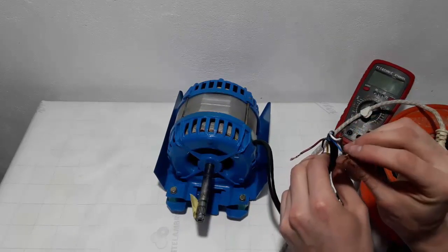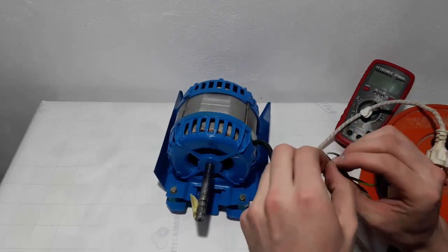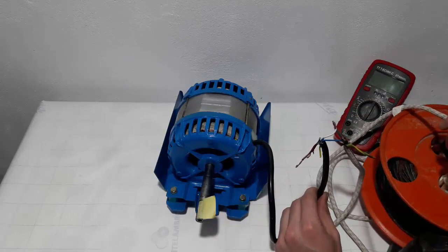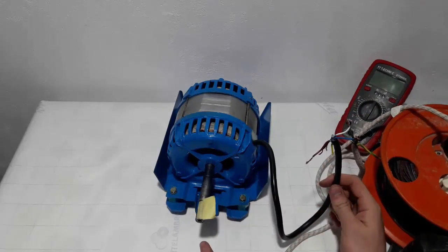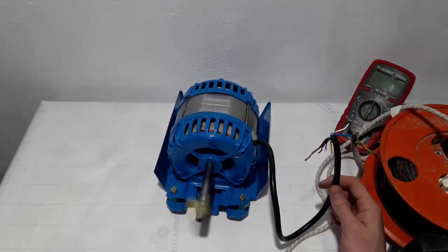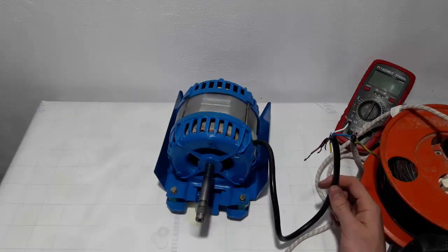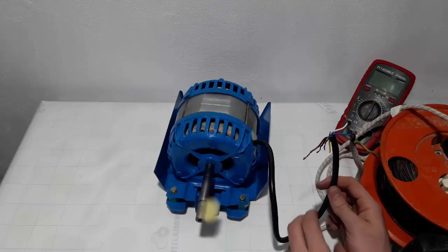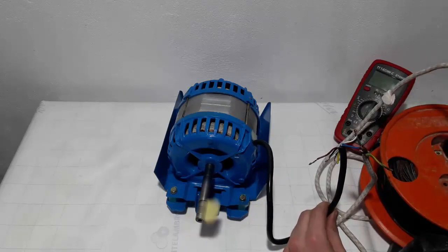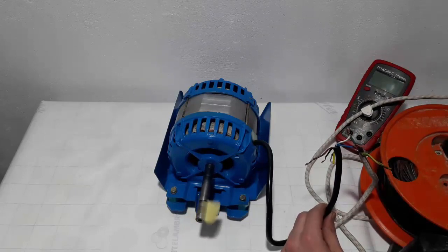For the high speed, we must connect the common and the blue. The motor turns faster but less than 2500 revolutions per minute. We also note that it's difficult to start and it must be helped by a small push on its arm.